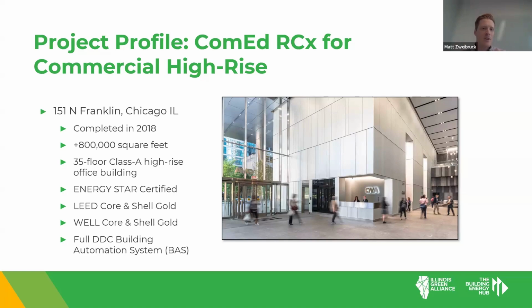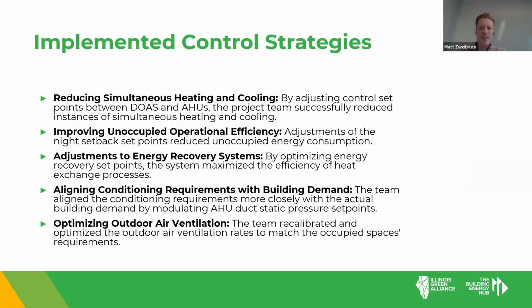We can go to the next slide. I won't have enough time to get into the specifics of the measures, but we did find a lot. When we got to this building, things were operating according to the sequences they were designed with. We didn't see things scheduled incorrectly, or overrides on set points, or something set a weird way and forgotten about, which we see in a lot of older buildings. In this case, what we saw in the sequences of operations matched the BAS.